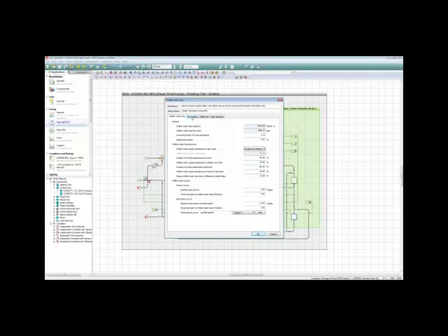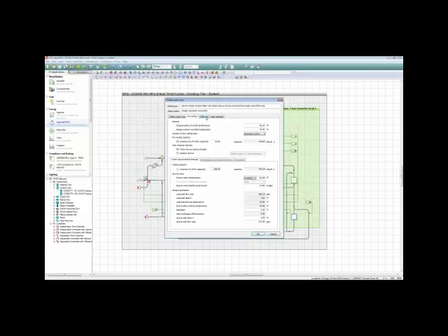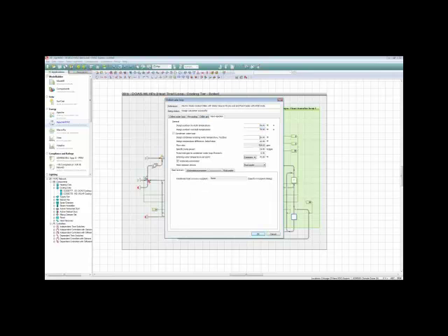And again, I wanted to mention here in the heat rejection side, just to clarify what I was saying before about design temperatures versus set points, you have some outdoor design conditions, and then you have a design condenser. You might say this is the condenser loop supply temperature, otherwise known as the condenser entering temperature, the temperature coming into the condenser tube bundle, including heat gain from the pump on that loop, and including contribution from whatever devices might be contributing to the heat rejection on that loop.